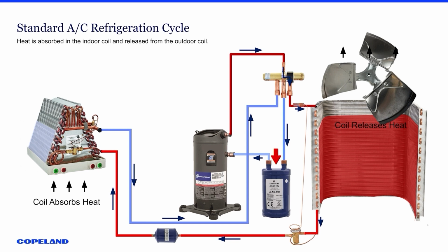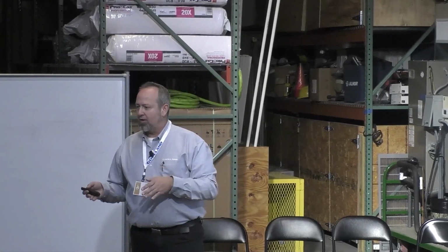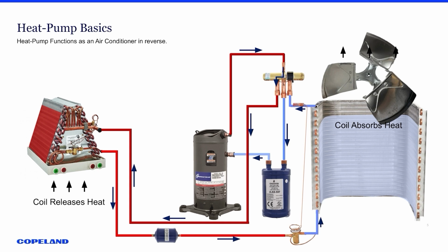Not as much, because a system that is designed for a specific tonnage or capacity will require more refrigerant in the cooling load than in the heating load. Less refrigerant in the heating load, and I'll explain why as we go through these two. And that's one of the things that makes a difference in matching the system and also in the system functioning and operating properly. The simple basics here, I'll just touch on them.